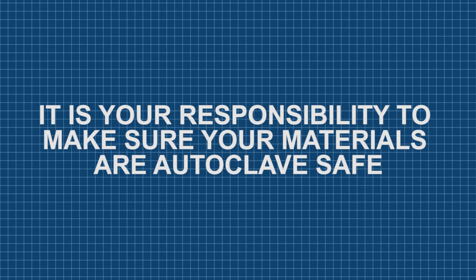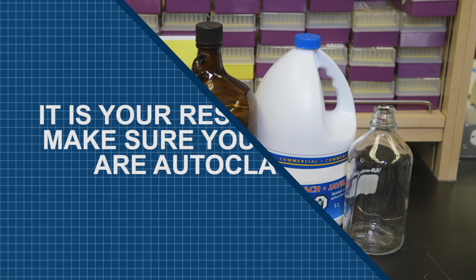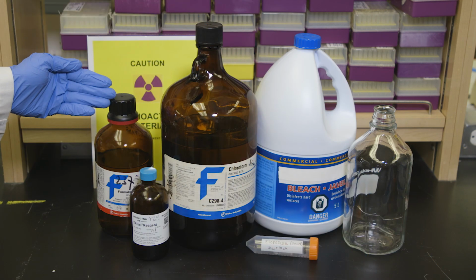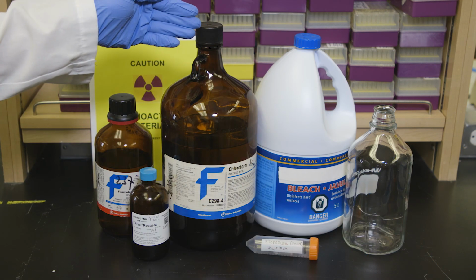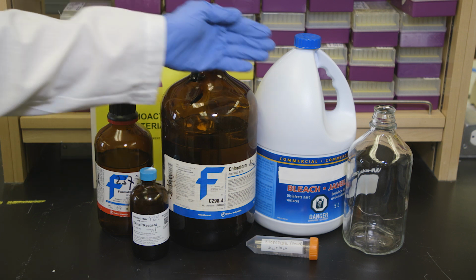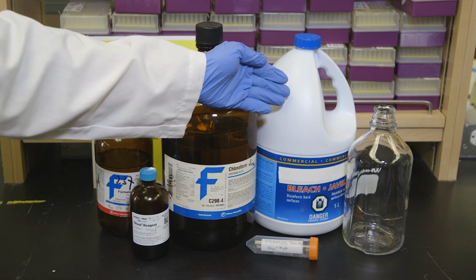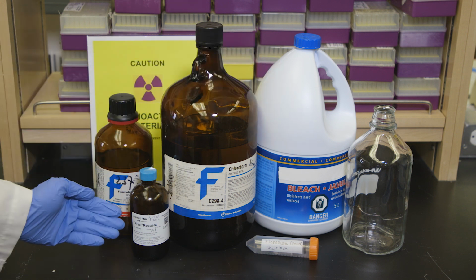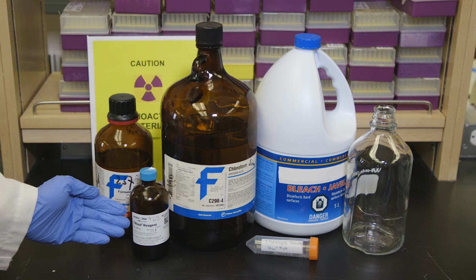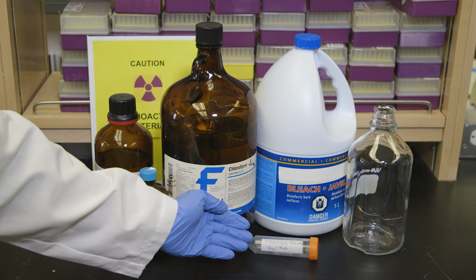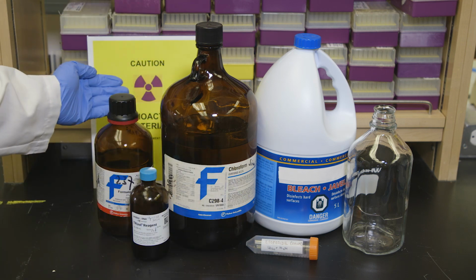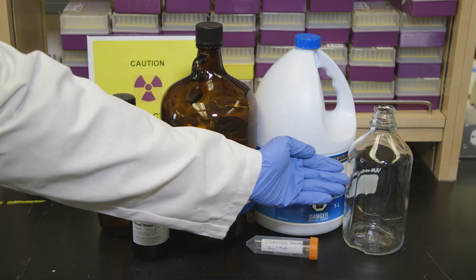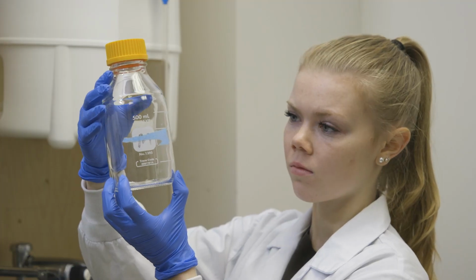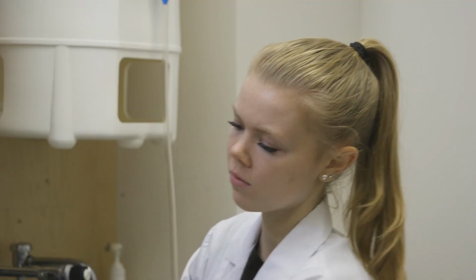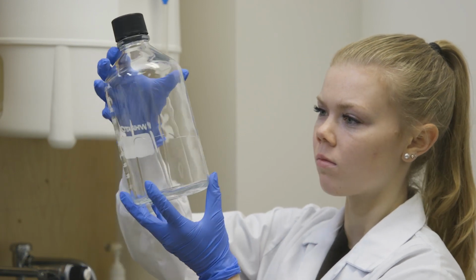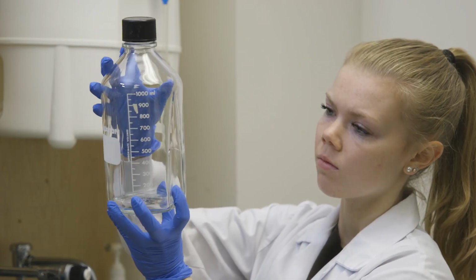The following are examples of items that cannot be placed in an autoclave: material that may emit toxic fumes, solvents, volatile chlorinated compounds such as bleach, corrosive chemicals such as phenol and trizol, material contaminated with chemotherapeutic agents, radioactive material, and cracked glassware. While glassware is safe to autoclave, it must be inspected for cracks prior to autoclaving. Failure to do so could result in glassware shattering during the sterilizing process.